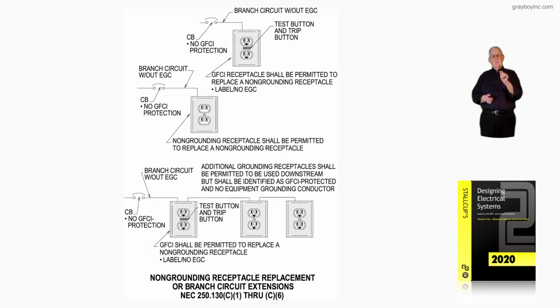And the GFCI receptacle shall be permitted to replace a non-grounding receptacle and be labeled "no equipment ground," so that the person using it knows it's a leakage current protection, but it doesn't have an equipment ground. That's what the GFCI receptacle would provide. Now, the next one is a branch circuit without an equipment ground and no GFCI protection, and we could replace it with a non-grounding type receptacle, 2-wire. And we would not have an equipment ground in that circuit naturally, but the receptacle doesn't require an equipment ground in this case.